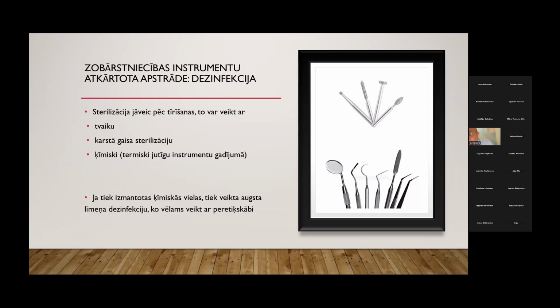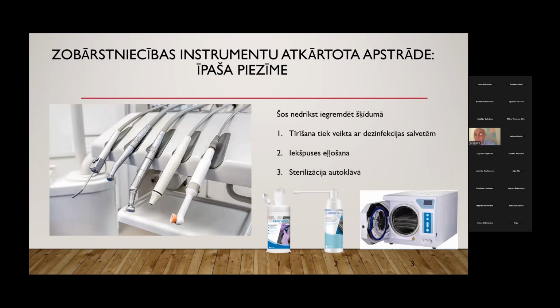So in case of use of chemical, we will need to perform a high-level disinfection, as we were talking with Gunther earlier, preferably with a peracetic acid. Because dental has one specificity: all those rotative instruments. So this should be a deep cleaning there.